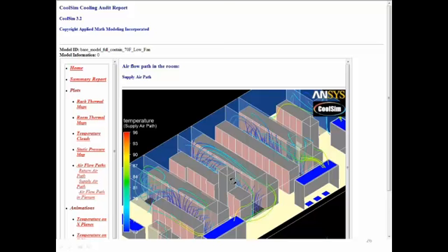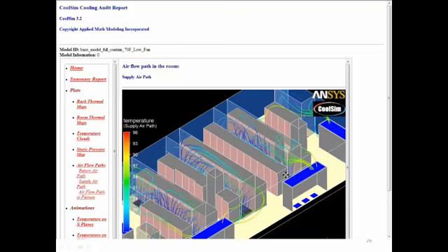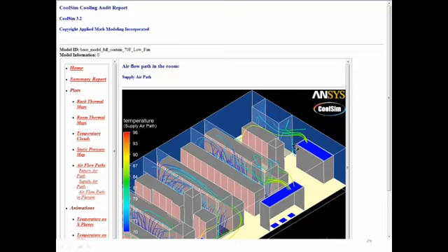And those few places I see over on the right there, where you can see some air coming from the cold aisle just going directly through the baffles and back into the rack. I mean, you're always going to see a couple of places like that. When you have excess air, yes.